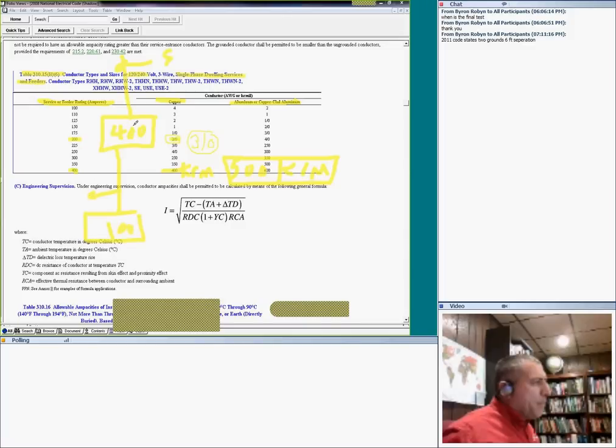So if I have a 400 amp panel, based on this it's going to be 400 kcmil, and for the feeder, I can get away with number 4. Three conductors, number 4. Three conductors, number 4 is good. So we'll do it in the notes. Okay, that table, make sure you know how to use it. Very handy, very interesting. Since we talk about residential, I thought it's worth mentioning. Before we leave the table, does anybody have any questions, guys? Any questions?